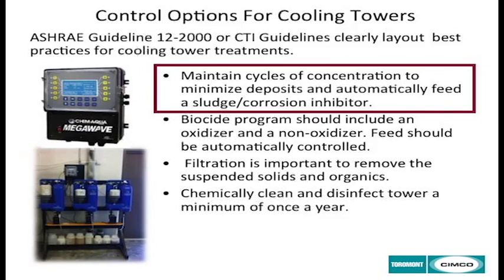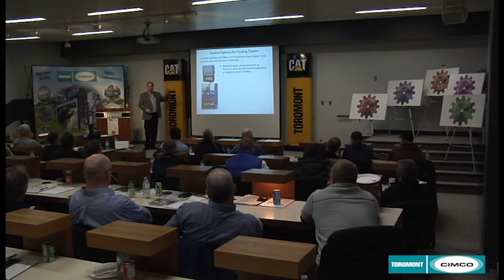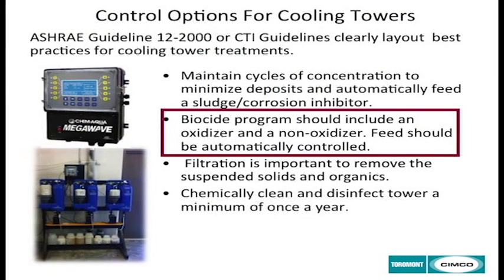Controllers like this one allow you to control your conductivity and cycles of concentration. So it has a conductivity probe and measures your cycles of concentration and automatically bleeds your system. It also automatically feeds your inhibitors to add the appropriate amount of chemicals to your system to keep those TDS from depositing. And it also adds the microbiological biocides that you need to maintain that microbiological growth or prevent Legionella from growing in your towers. So biocide programs should include an oxidizer and a non-oxidizer. Feed should be automatically controlled.